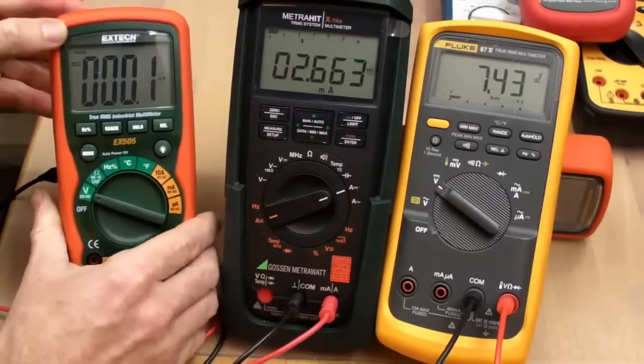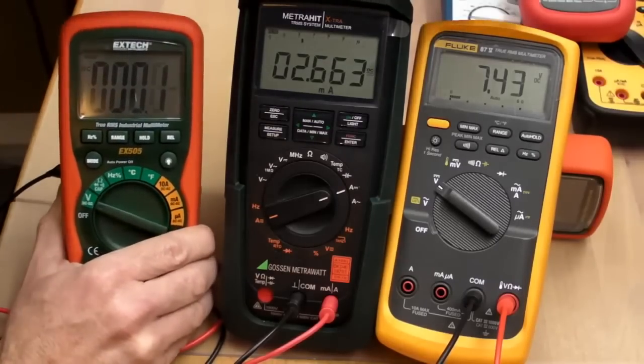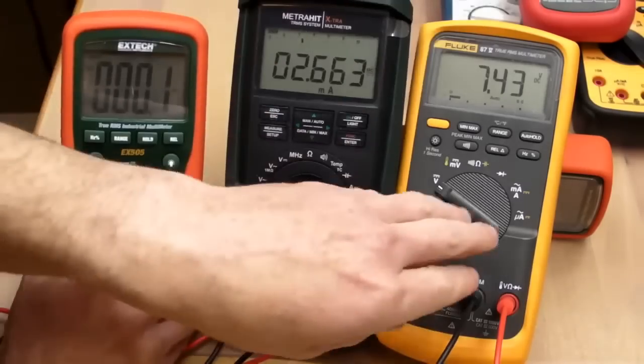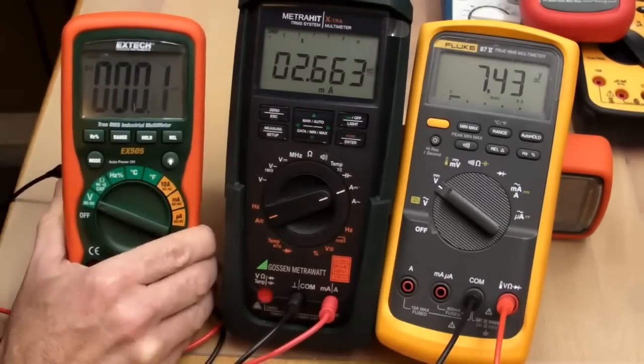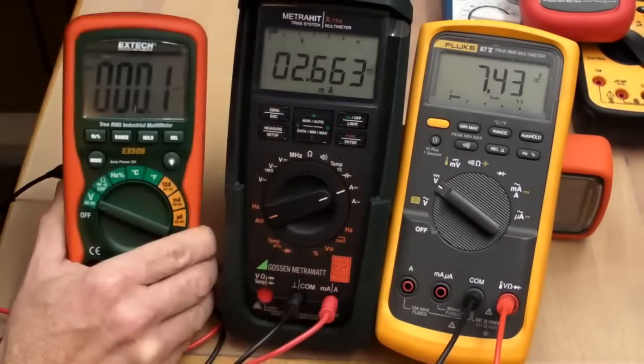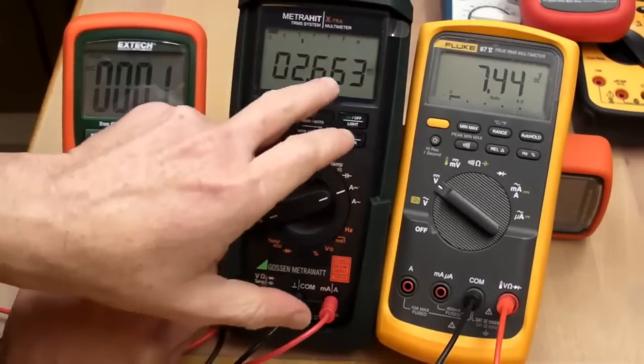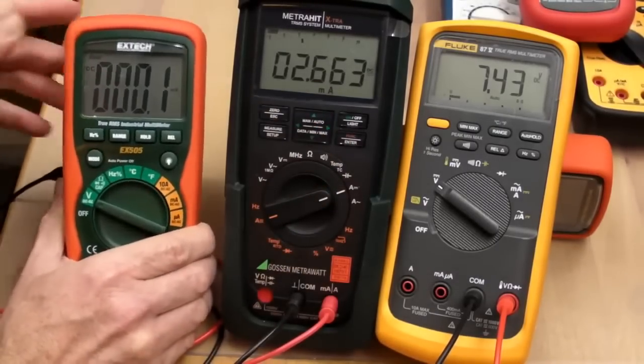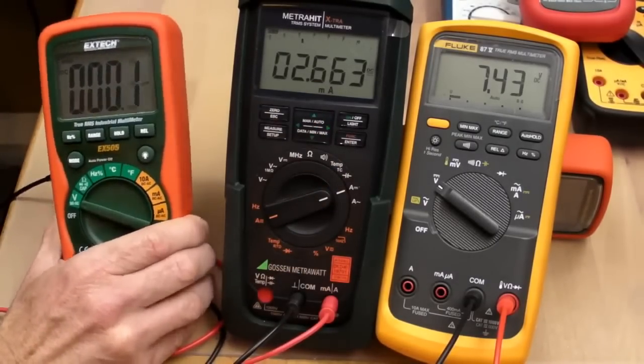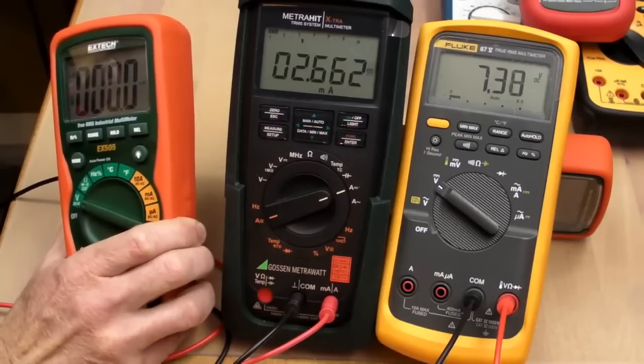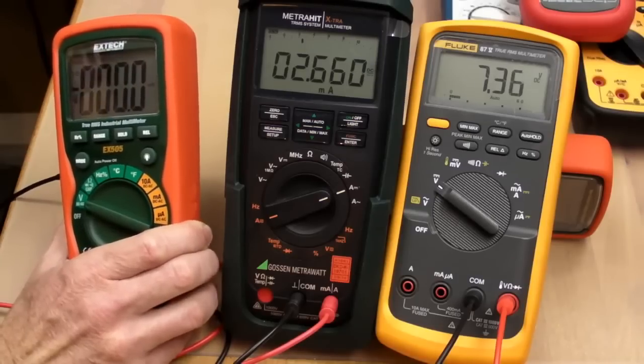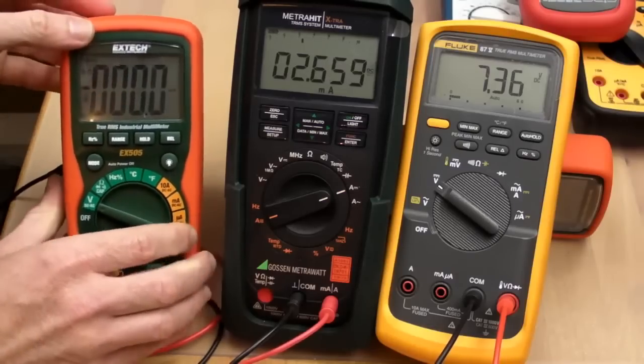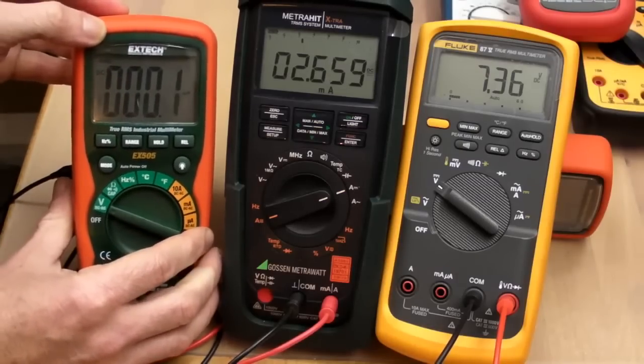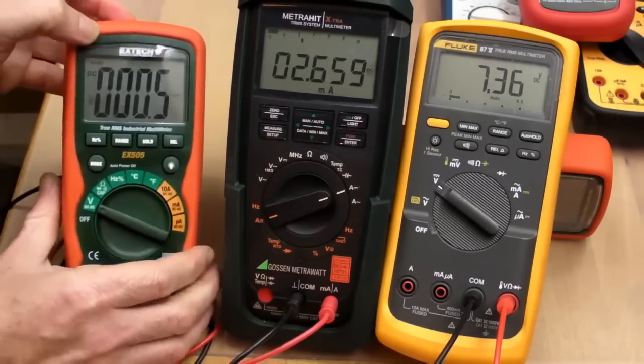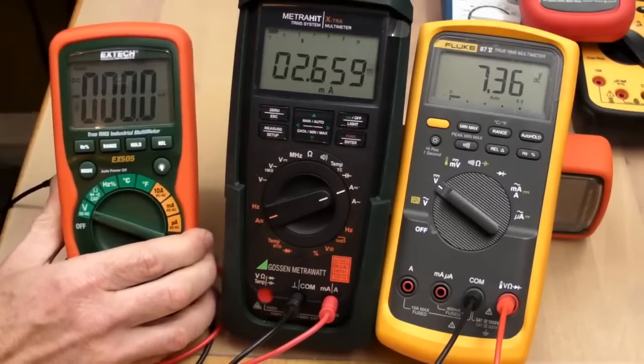Let's measure the battery consumption of the Extech. I've got the Fluke 87 V set up here to measure the input voltage, coming from an external power supply, and the MetraHit Extra here measuring the battery current. Let's wind the voltage down to see where the low voltage icon comes on. There we go, it comes on at about 7.36 volts. That's not very good, that's 1.2 volts or more per cell, so it doesn't go down that low. I'm not terribly impressed by that.